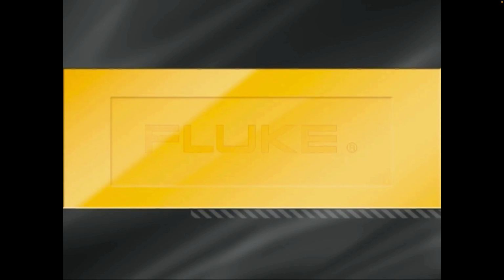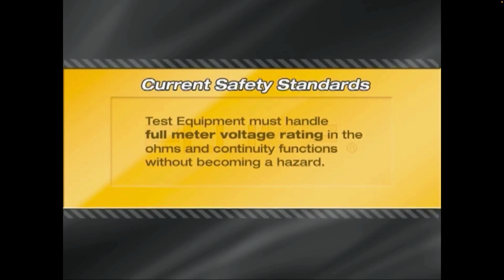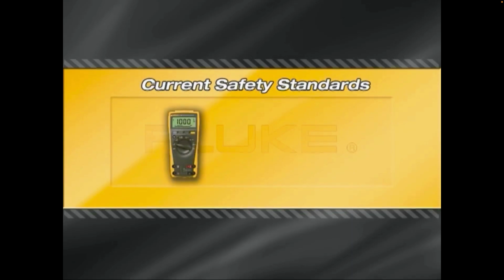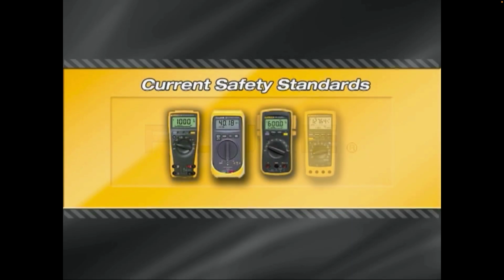This principle is so important that it has been written into current safety standards. The standards require that test equipment must handle the full meter voltage rating in the ohms and continuity functions without becoming a hazard. To meet the demands of today's high-energy, high-hazard workplace, quality manufacturers have re-engineered their test instruments to make them more reliable and far safer.